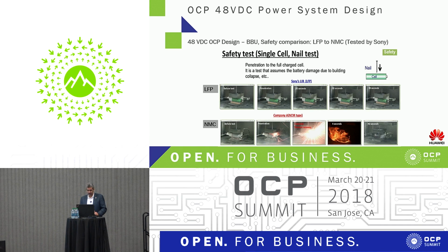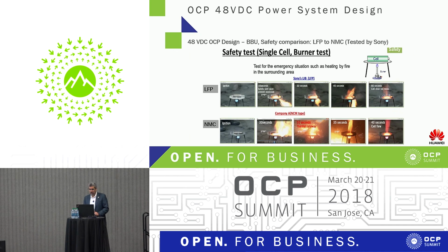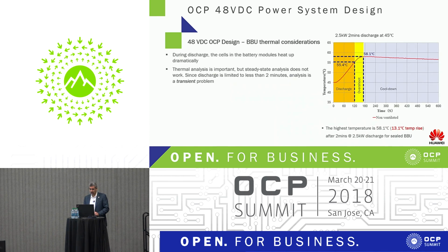Generally, we want to avoid that in data centers. Another test is a burn test. Again, the iron phosphate is a pretty controlled event, whereas with the nickel cobalt, the cell is actually gone from the picture, it blew up and flew out of frame, whereas the iron phosphate's still there. So overall, we think iron phosphate is the safer chemistry. It's the best balance of safety, capacity, cost, and everything we'd look for in a data center.